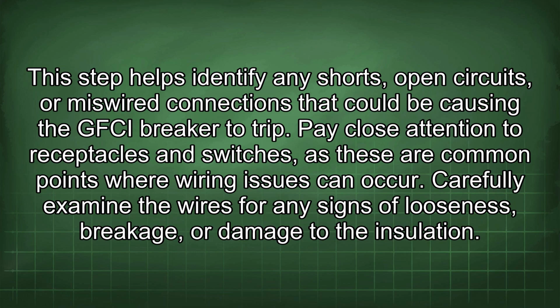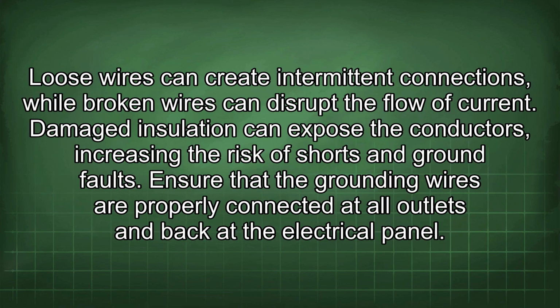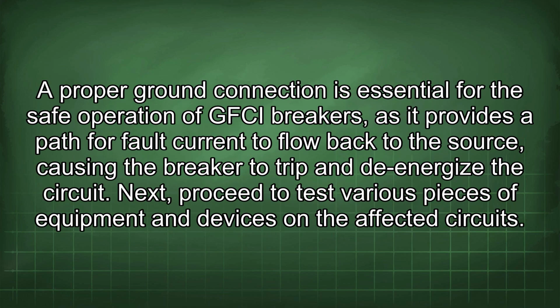Carefully examine the wires for any signs of looseness, breakage, or damage to the insulation. Loose wires can create intermittent connections, while broken wires can disrupt the flow of current. Damaged insulation can expose the conductors, increasing the risk of shorts and ground faults. Ensure that the grounding wires are properly connected at all outlets and back at the electrical panel. A proper ground connection is essential for the safe operation of GFCI breakers, as it provides a path for fault current to flow back to the source, causing the breaker to trip and de-energize the circuit.